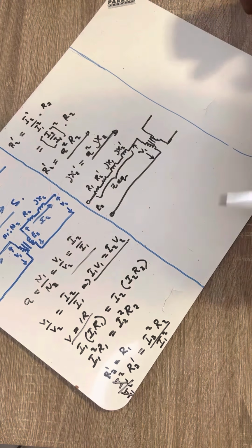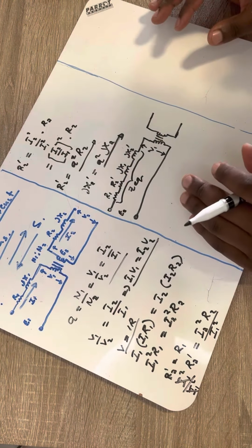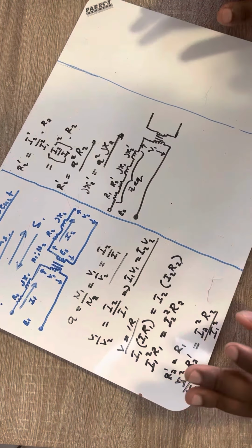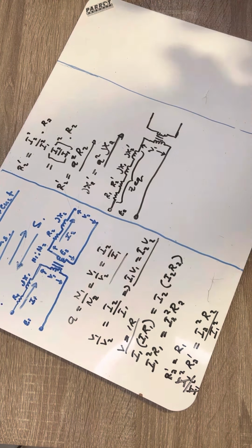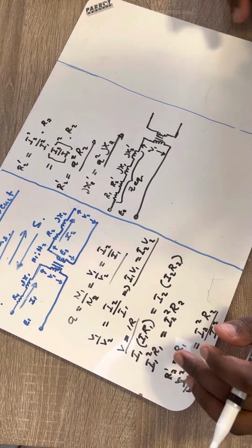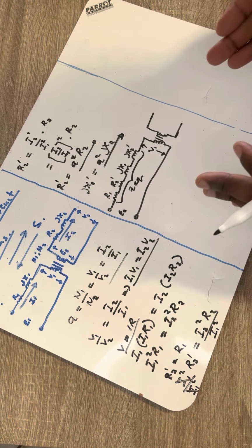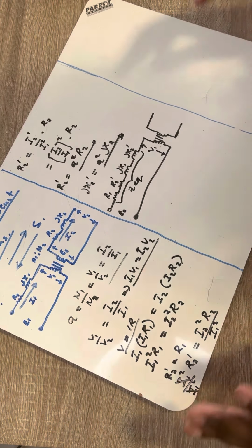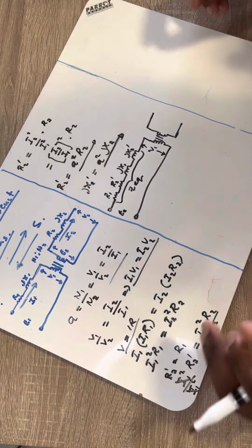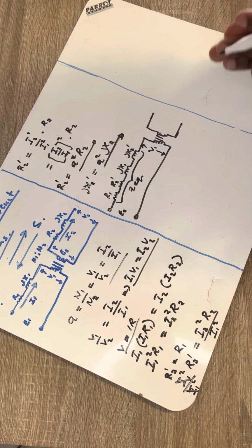So basically, why are you doing this? If you're given values for the primary and also the resistance and the reactive values, and you are not given anything for the secondary terms of voltage and current, you can calculate the total impedance of the transformer on the primary side. Then you calculate the current as well as the secondary voltage using the voltage on the primary.